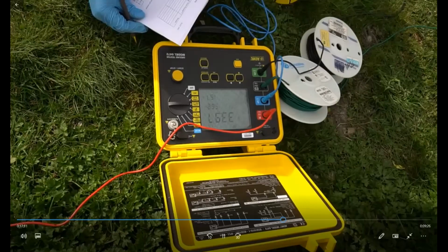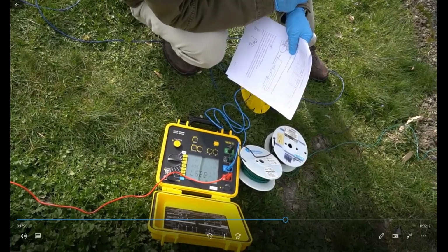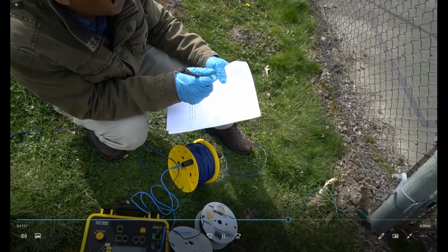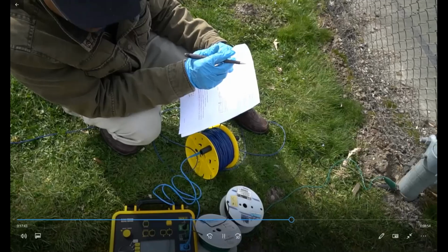Okay, so from this reading we can get that if the short circuit current is equal to 16.7 milliampere, then the resistance between the grounding grid and this probe is 33.97 ohm.